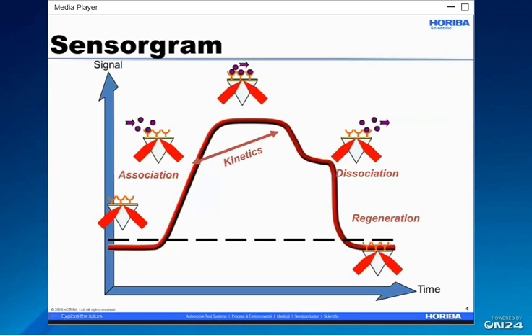During an SPR experiment, one of the interactants is immobilized to the sensor surface, while the other is free in solution and passed over the surface. Association and dissociation is measured in arbitrary units and displayed in a graph called the sensorgram. Biomolecular interaction analysis is not limited to proteins — you can measure DNA-DNA interactions, DNA-protein, lipid-protein, and hybrid systems of biomolecules and non-biological sensitive surfaces can also be investigated.